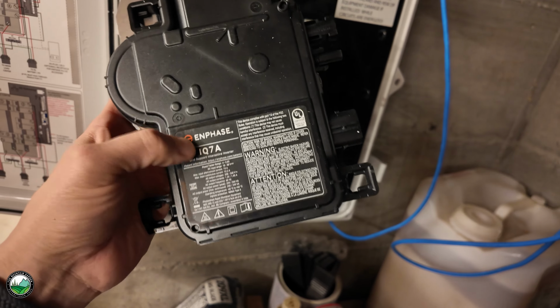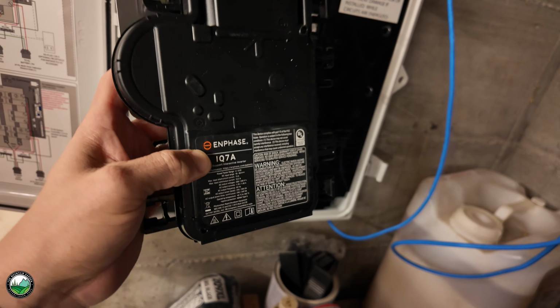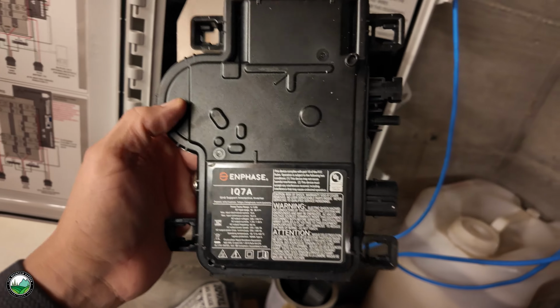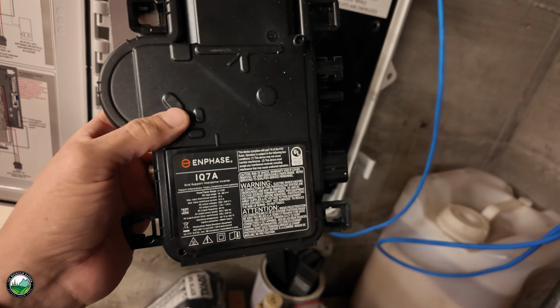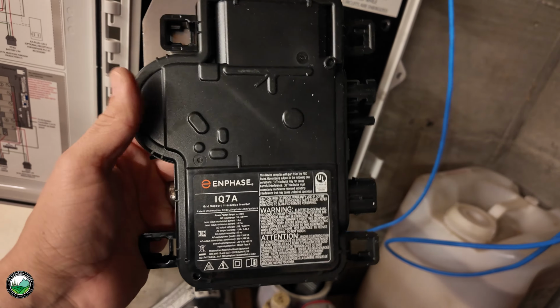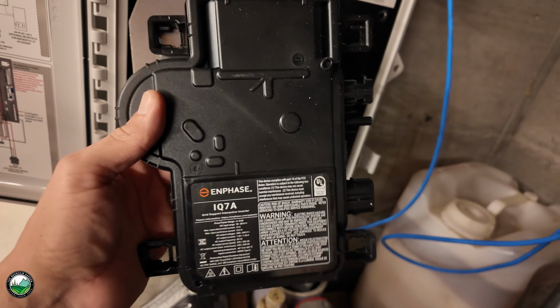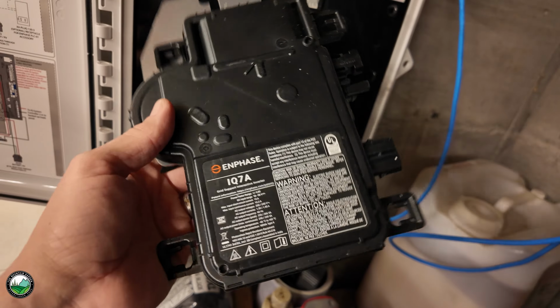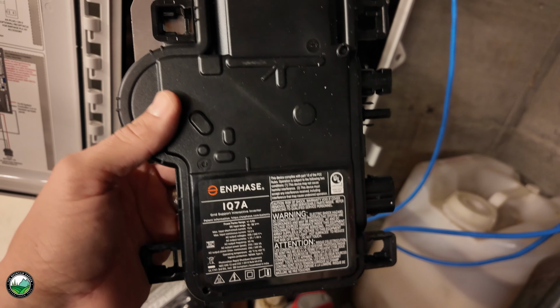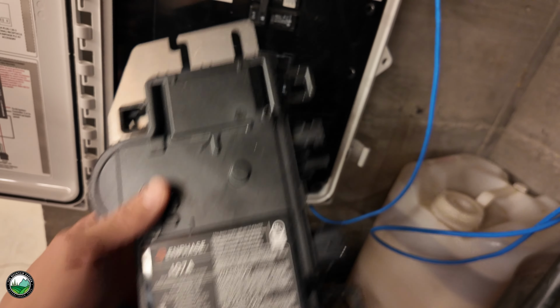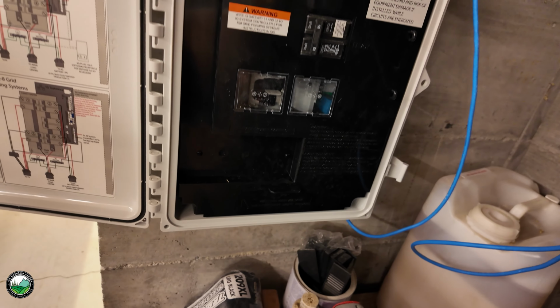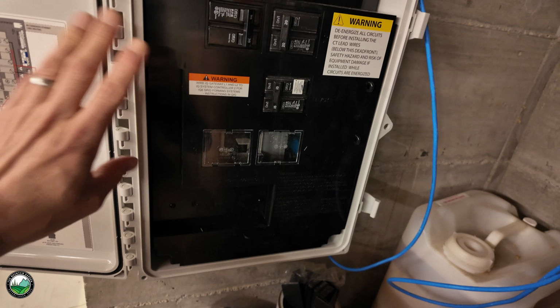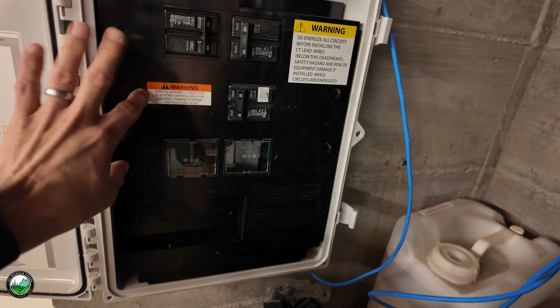Now, the IQ7A, these are good for about 345 watts maximum. So theoretically, if you could actually get those panels to produce 400 watts, this would not be able to invert all that. You'd be limited to about 340, 345 watts. I don't think that's too big of a problem because the likelihood of them ever hitting their nameplate capacity is pretty darn low. One thing I did like, though, is that installing the IQ7A microinverters as well as the combiner box was actually pretty easy on a DIY side of things.